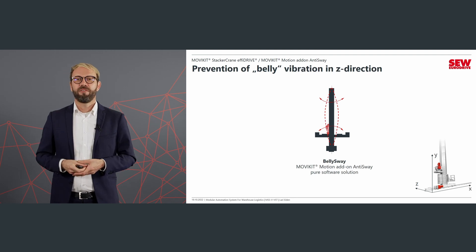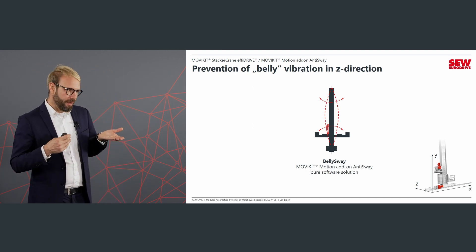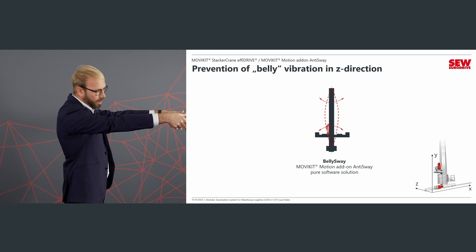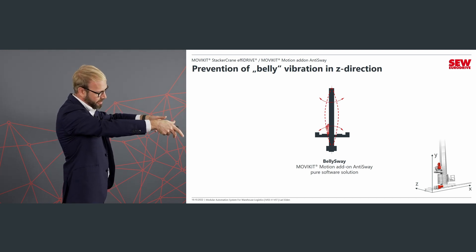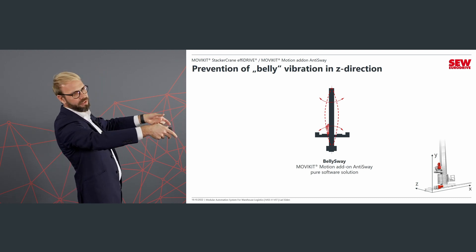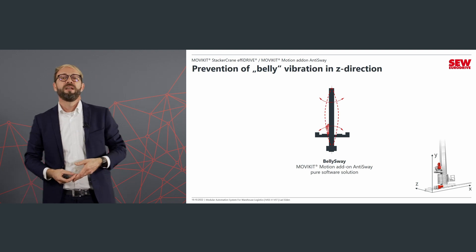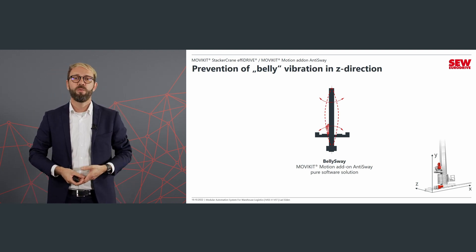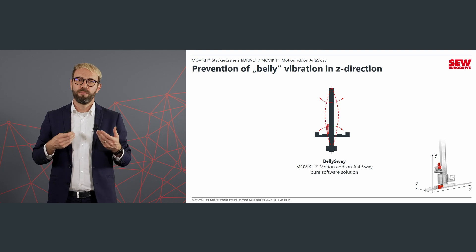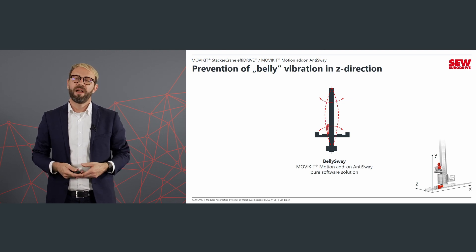The next vibration I want to talk about is in the Z direction — the direction of storage. This vibration occurs when you pull a box out of storage, because the friction between the shelf and the box pulls the tower in the direction of the storage, creating what we call a 'belly.' That's why we always refer to this as belly sway. This can be solved with the same solution as tower sway: the MOVIKIT Motion add-on AntiSway, which is also fully parameterizable with physical values, so commissioning can be done very quickly.